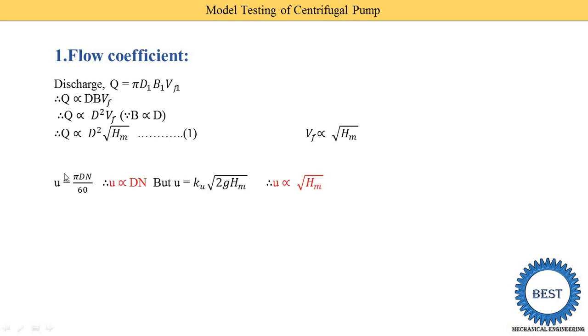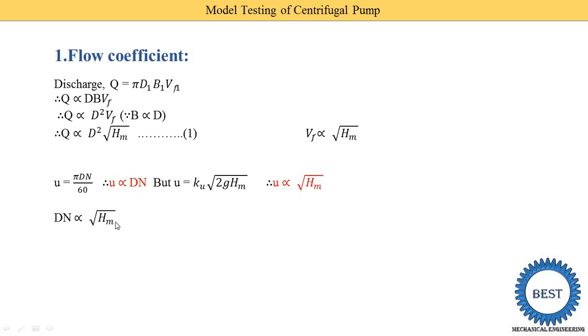We also know that U = π·D·N/60, meaning tangential velocity equals π × diameter × speed divided by 60. Since π and 60 are constants, U is proportional to D·N. We also know that U = KU × √(2g·HM). Since KU, 2, and g are constants, U is proportional to √HM. So from these two relations, D·N is proportional to √HM.